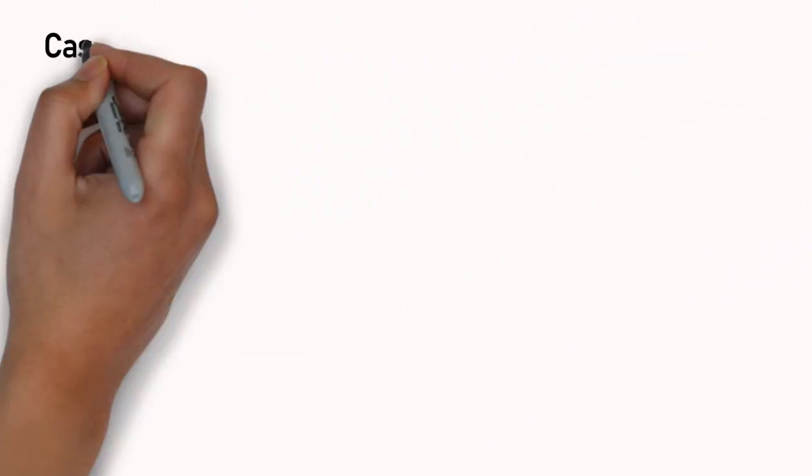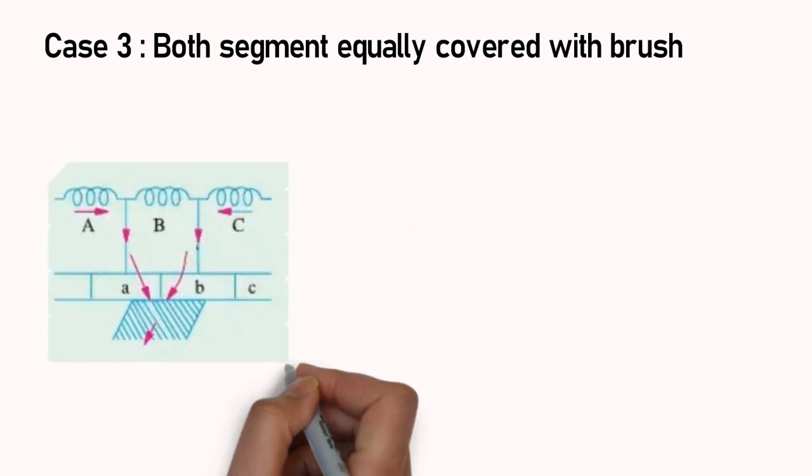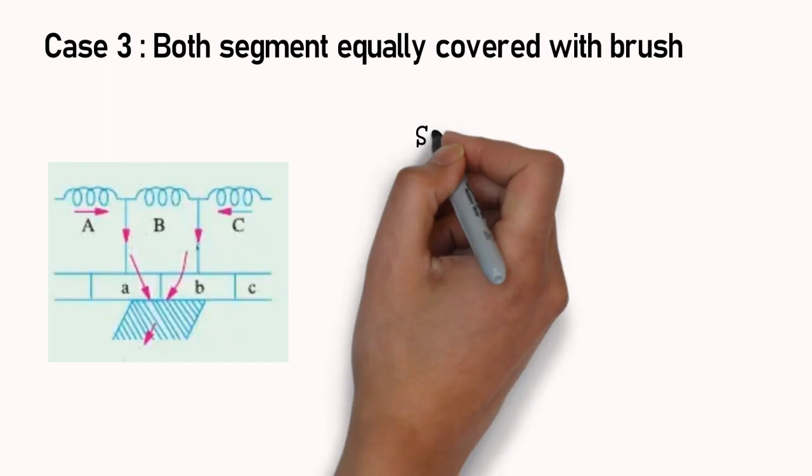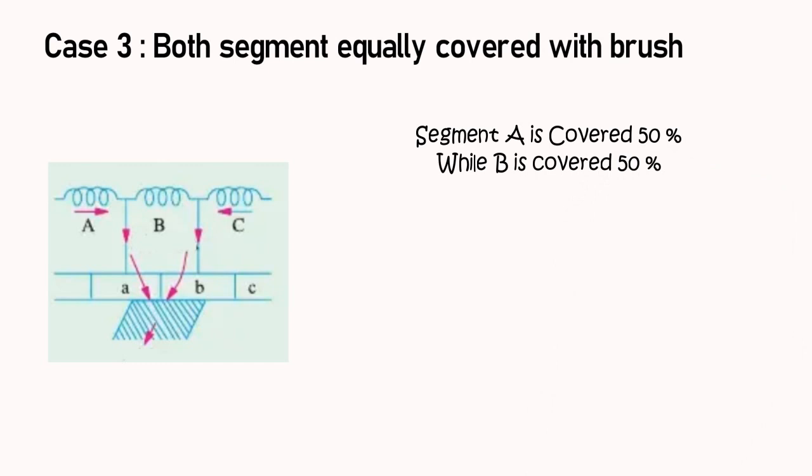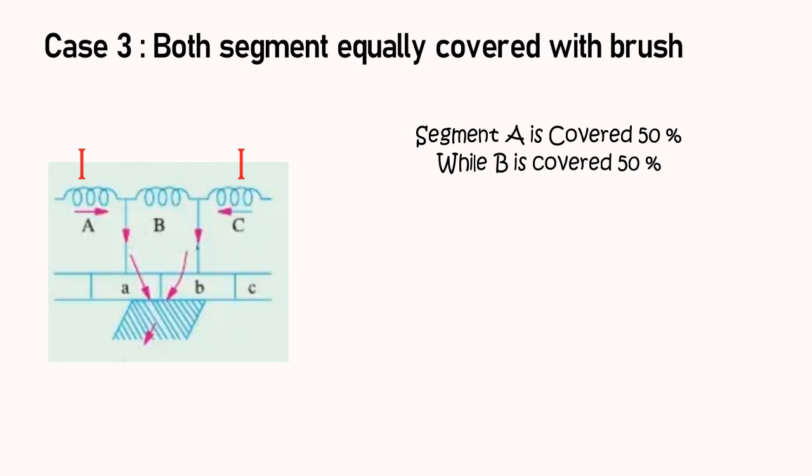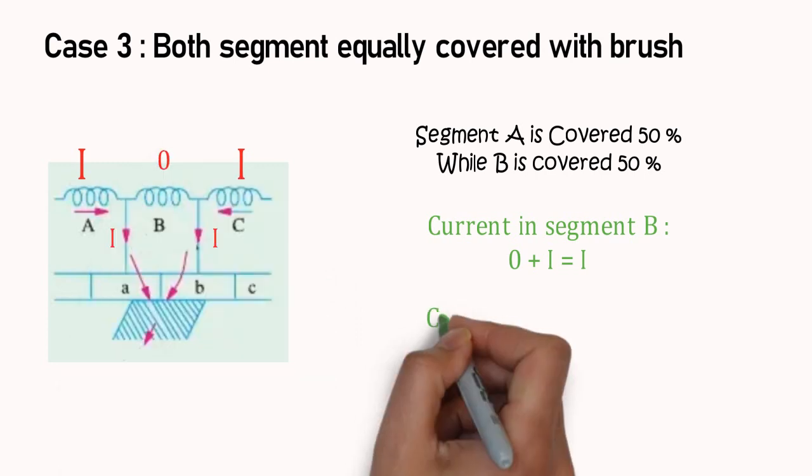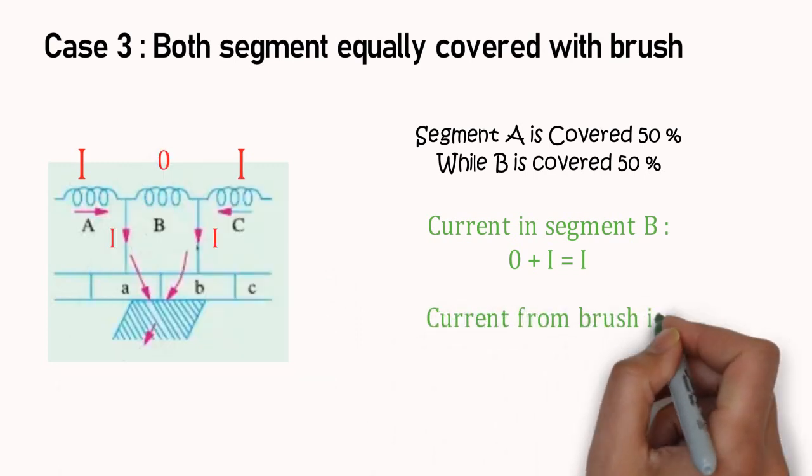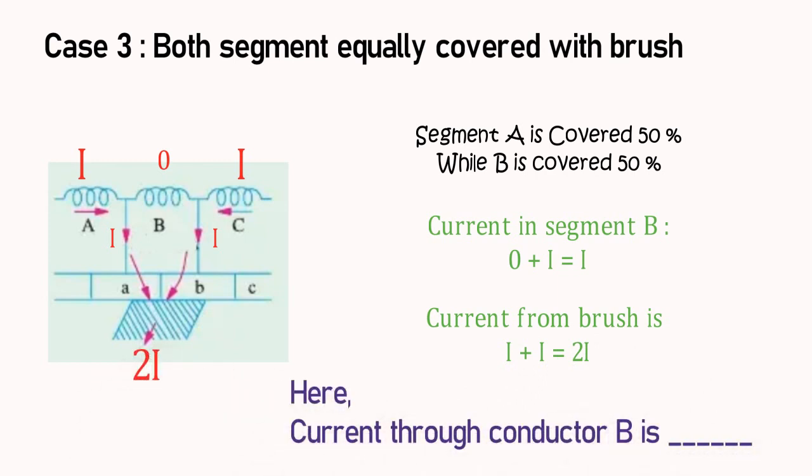In this case, contribution of both commutator segments are equal. So, same amount of current will pass through commutator segment A and B. Again, coil A and coil C is having same current that is I. As both segments equally connected with brush, no current is passing from coil B, and full current 2I is passing through brush.